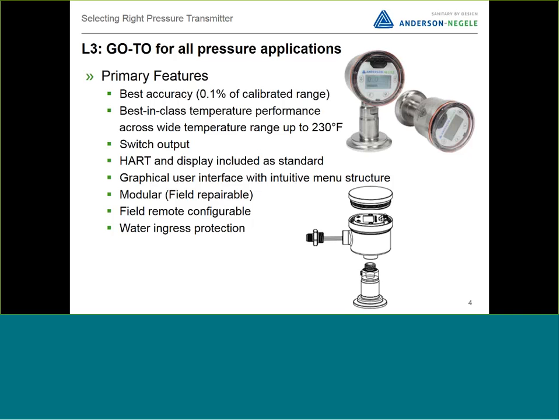The L3 also comes with HART and a display as standard, and you could configure the sensor for different settings, the range, alarms, display unit, and all these features using both the local display and the HART handheld or your HART module from your PLC.